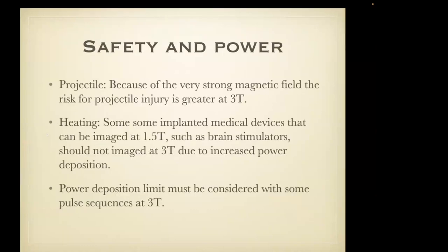When you go to a more powerful magnet, the risk from projectiles in the scanner room goes up. Certainly in the United States there have been numerous accidents in MR scanning rooms, and I would say the majority of them go unreported. I remember one day at work passing by one of the scanner rooms and you could see the handle of a mop sticking out of a scanner, and they had hung a curtain on the window so people didn't notice. These accidents do occur, and the risk to the patient is greater at 3 Tesla because of the stronger field strength.